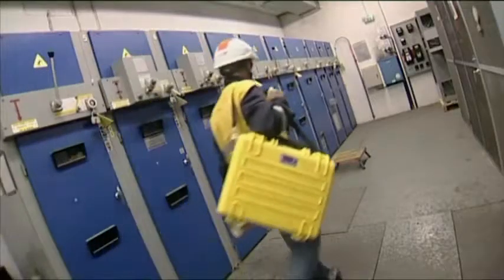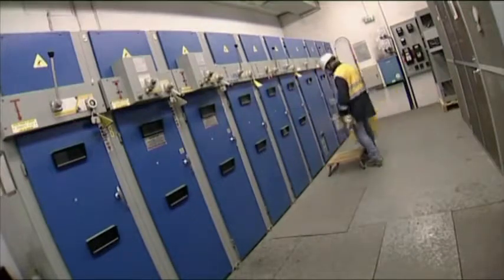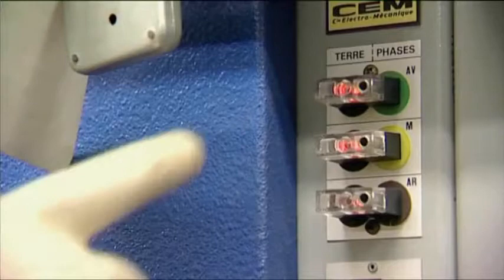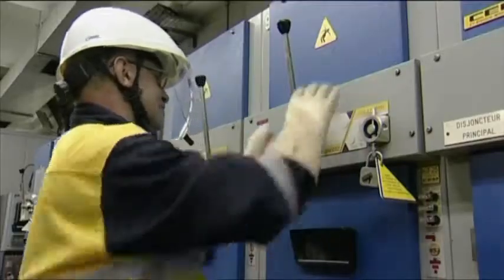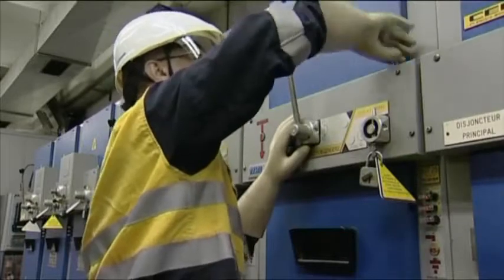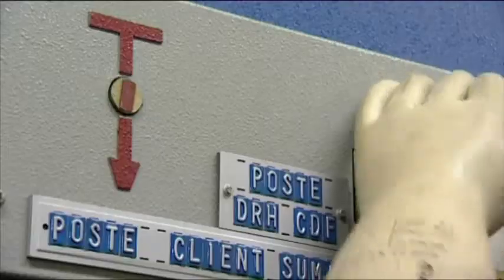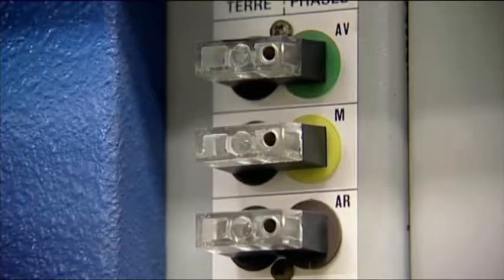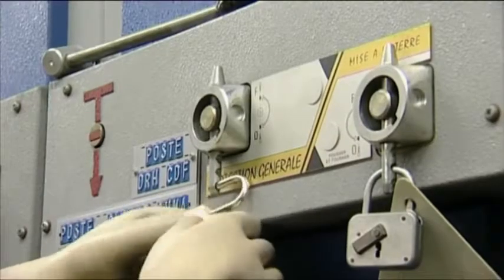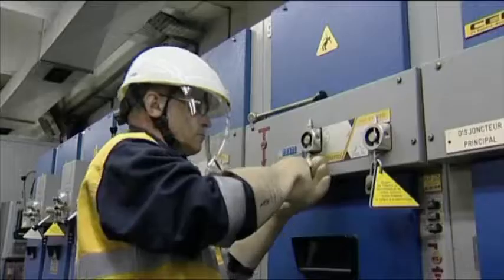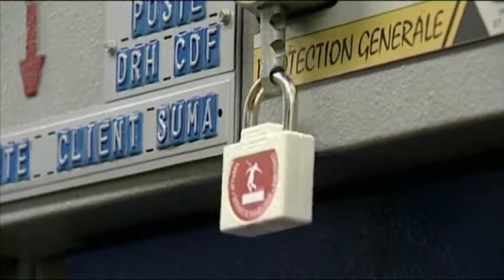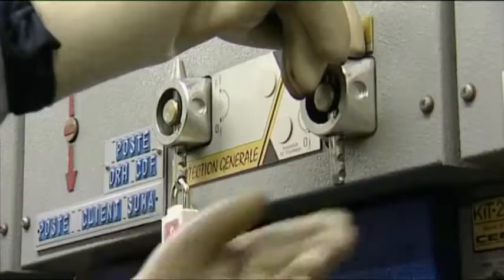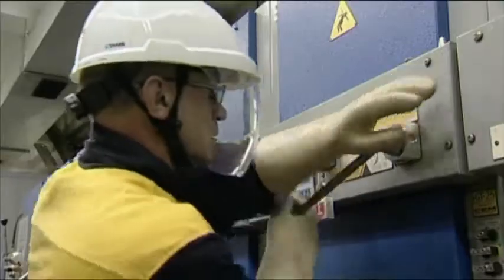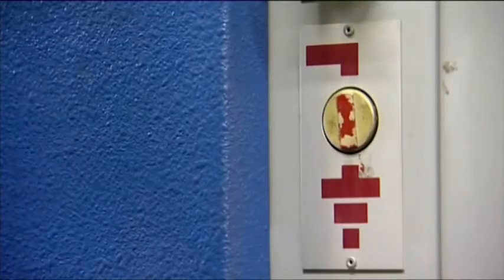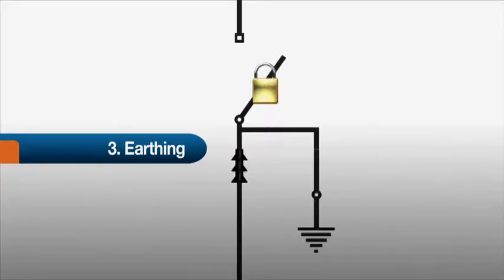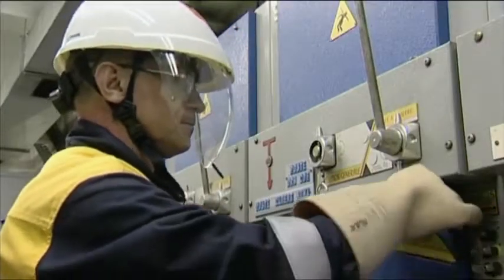The disconnection operator then repeats this procedure in Substation 2. He's about to open the second switch and to lock it by using one of his disconnection padlocks. The cable is now isolated from the power source and locked at both of its ends. We can now close the grounding switch. Once the cable is grounded, and only at this point, can we consider it actually has no voltage.